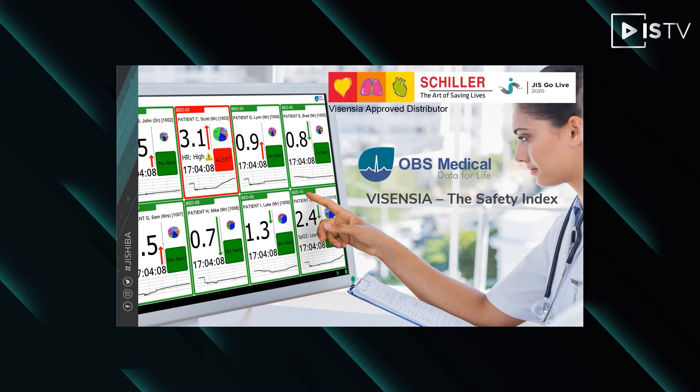Visensia works by comparing the patient's vital signs — heart rate, respiration rate, blood oxygen, temperature, and blood pressure — to a large unique training database. These data are organised as a correlated set of data, not multiple independent measurements. The comparison permits Visensia to spot patterns of instability based on real-world patient data, patterns that in some instances cannot be picked up by single-channel alarm systems or overstretched nursing staff.